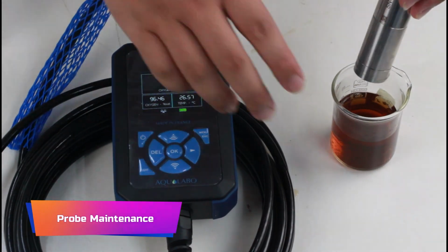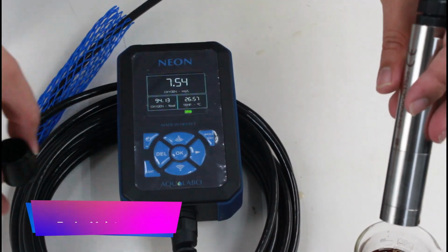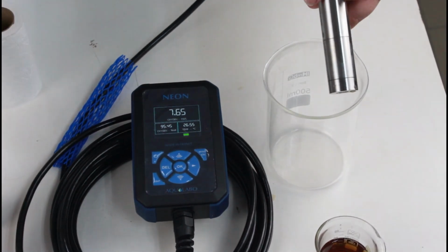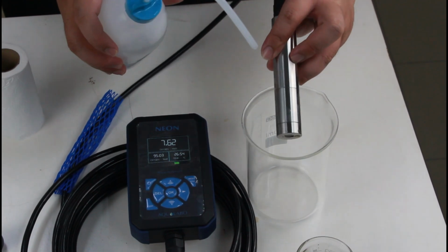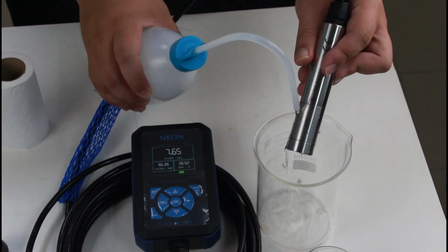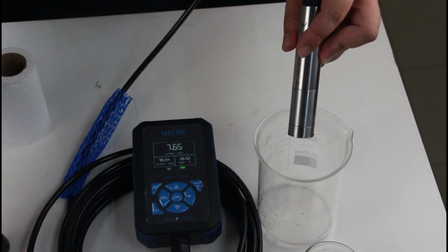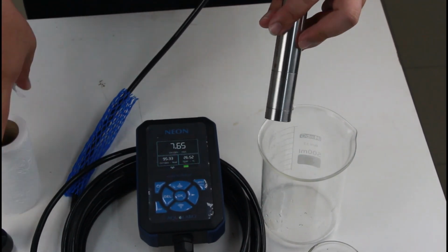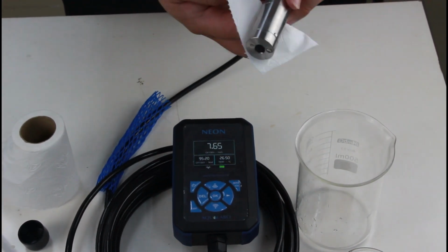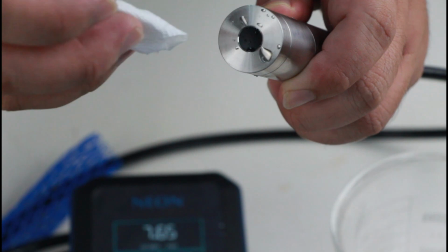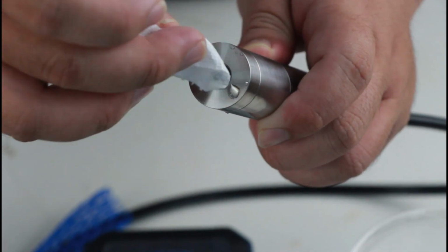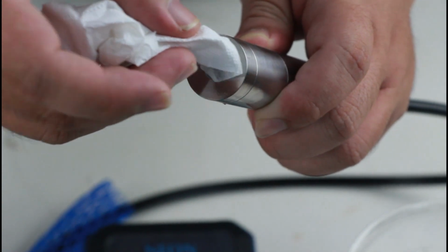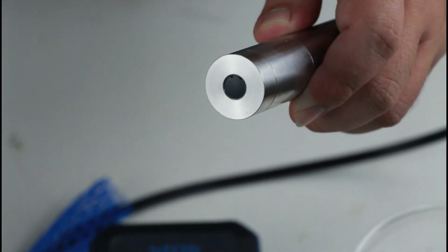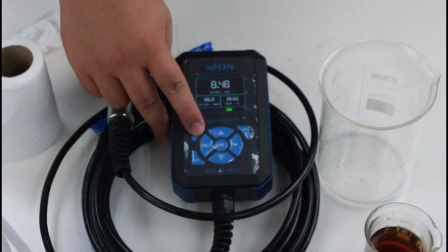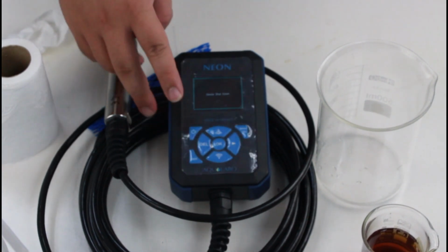Okay, after testing a sample, we need to put the probe back into the cap here. But first, we need to clean it with distilled water, or tap water also can. We just clean it. After that, use the tissue paper to wipe off the excess water. And be careful on this black area here. Make sure you don't wipe it, you just touch it with your tissue paper. After that, you keep it back inside the cap and switch off the unit. By pressing the off button, it will show device shut down.